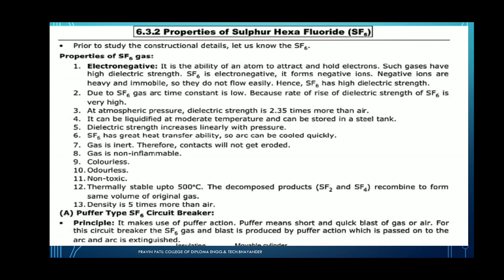Next property of SF6: SF6 has great heat transfer ability, so the arc can be cooled easily as well as quickly. Arc quenching takes place with the help of SF6. The gas is an inert gas, therefore the contacts do not get eroded. This gas is non-inflammable.